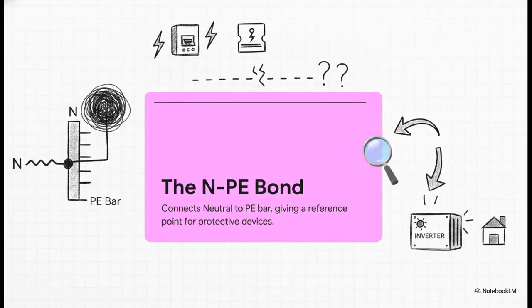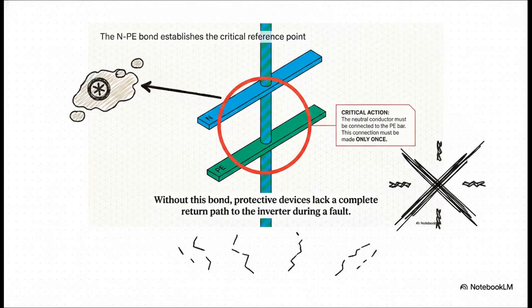This is arguably the most crucial and, honestly, the most misunderstood step in the whole process. By physically linking the neutral conductor directly to the protective earth bar, we are establishing a vital reference point. Without this specific link, your circuit breakers and RCDs are essentially flying blind. They completely lack a return path to the inverter during a fault, which means they literally won't even know a fault is happening. It requires absolute precision. You have to physically connect the neutral and the protective earth.